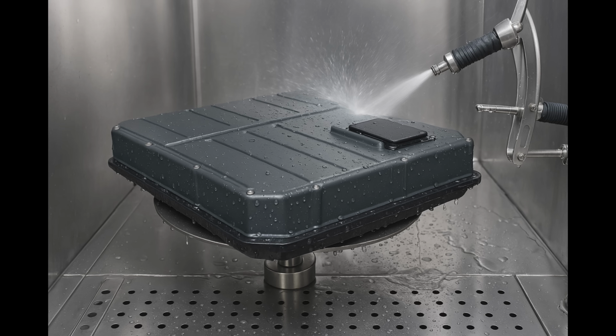Results measured include ingress detection using humidity sensors or desiccant patches, post-test insulation resistance checks, functional tests of BMS, pressure sensors, and any external mounted components, and connector seal integrity verification. Real-world risks of IP69K failures include water forced past gaskets at high velocity, especially at connector pins or vent ports, hot water degrading polymer seals or adhesives, jet erosion of pressure relief membranes, false BMS triggers due to shorted signal lines or sensor anomalies, and it could also lead to thermal runaway.